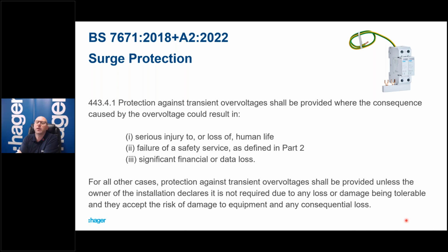Okay, now what we're finding is a lot of contractors aren't having that conversation with the client, they're just opting to put the SPD in. Quite often they might not even get to speak to the client if they're working for a builder or whatever. Most of the time they're considering it to save the comeback, any backlash with this, or documenting that decision, they just install that. Now, there were some changes to the regulation when we had the corrigendum earlier in the year.